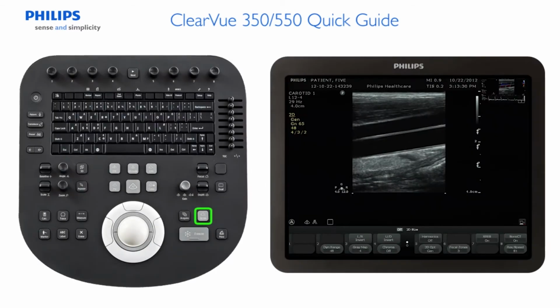iScan Intelligent Optimization is used to automatically optimize the 2D gain, the color gain, and the pulsed wave Doppler. For this next demonstration, we will overgain the image. With one press of the iScan button, the 2D iScan optimization evaluates grayscale distribution to optimize the TGC and 2D gain settings for the current image.